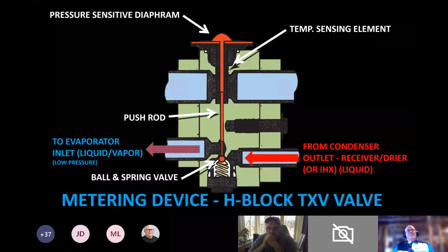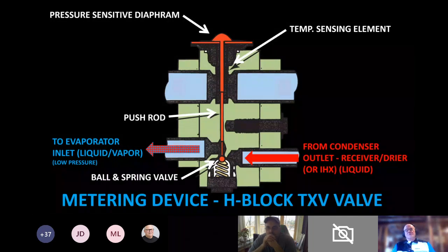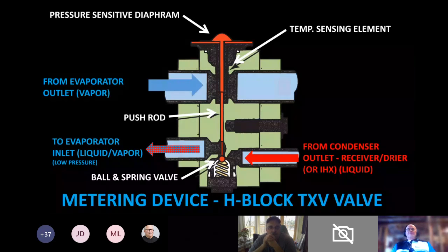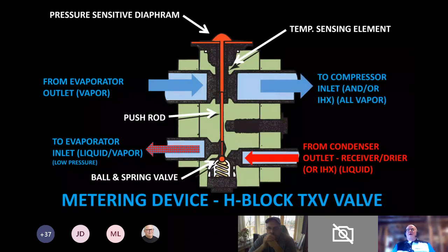It comes out of the evaporator as a vapor, and it's immediately sensed the temperature by the temperature sensing unit, which then controls the flow of refrigerant by opening and closing that ball valve or modulating it. It leaves the H block and goes to the compressor inlet or the IHX if it has one installed, and it's all vapor. Now, these animations that you see, I'm going to share them with you in a PowerPoint.